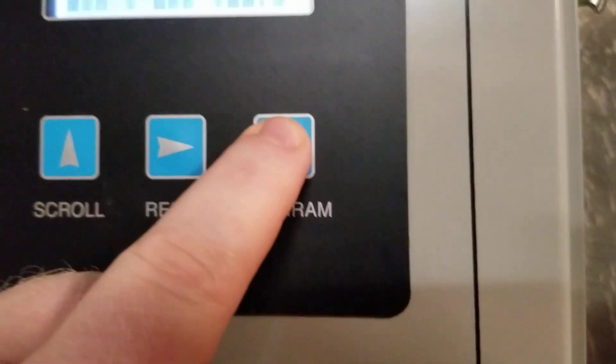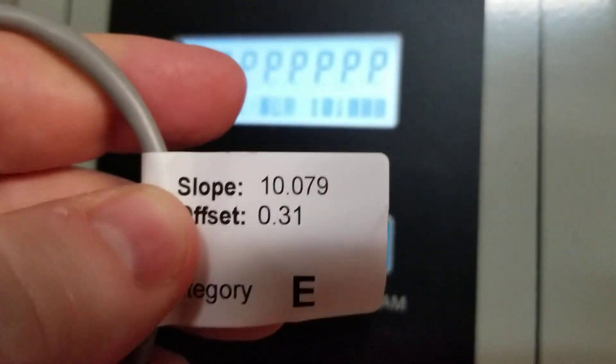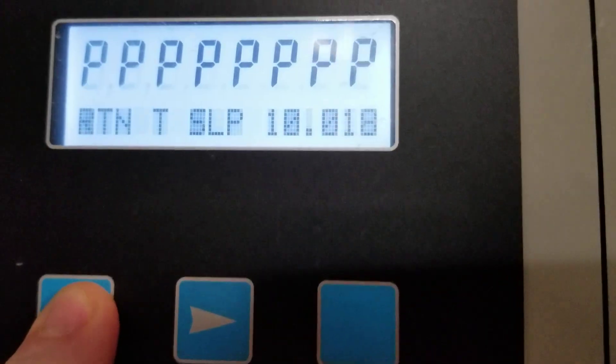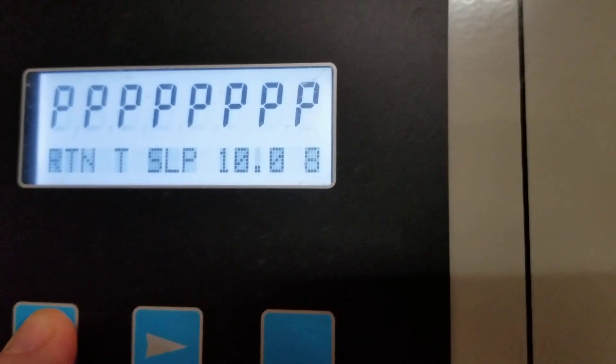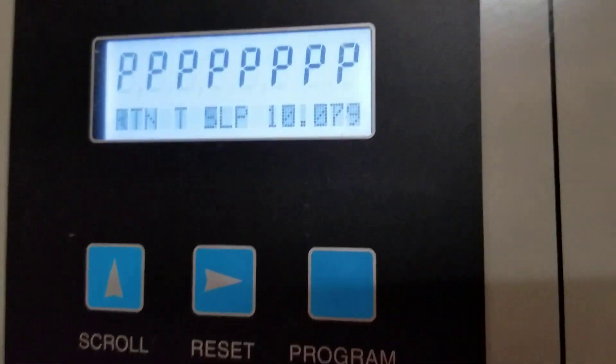The next step, I'm going to press the program button again and it's going to take me to the slope value. Again, our tag — our slope value is 10.079. Currently it's 10.018, so we're going to change this also. I'm going to arrow over until I get to the right digit, then arrow up to change that digit. You would do this exact same step for the supply temperature sensor as well.